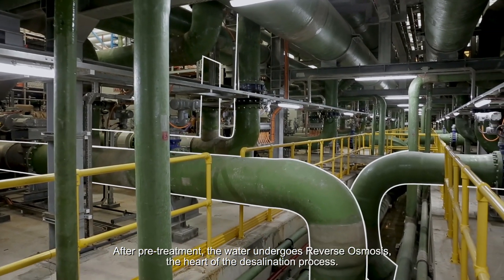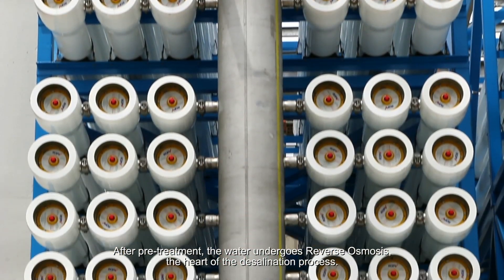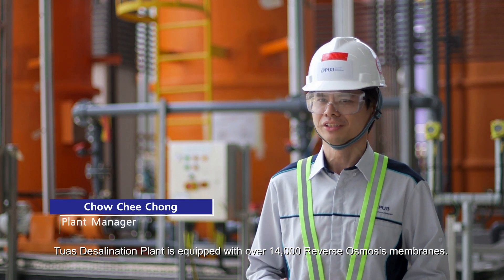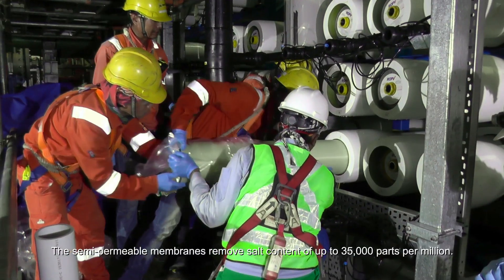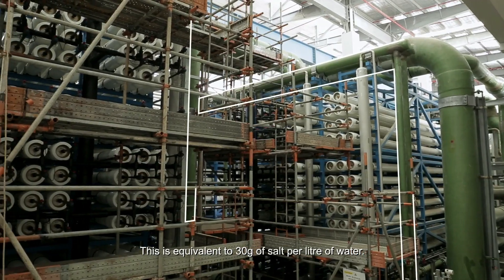After pretreatment, the water undergoes reverse osmosis, the heart of the desalination process. Tuas Desalination Plant is equipped with over 14,000 reverse osmosis membranes. The semi-permeable membranes remove salt content of up to 35,000 parts per million, equivalent to 30 grams of salt per litre of water.